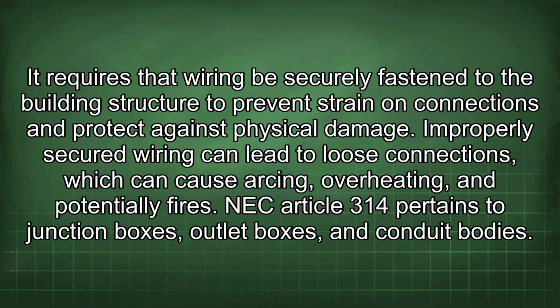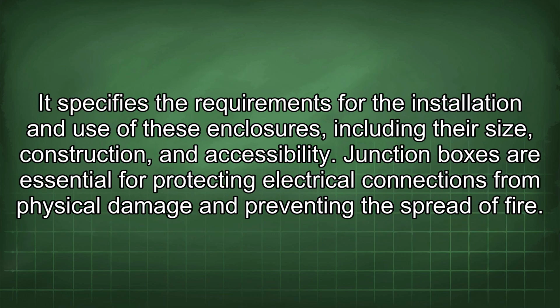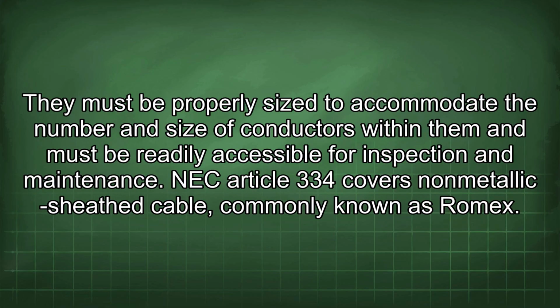NEC Article 314 pertains to junction boxes, outlet boxes, and conduit bodies. It specifies the requirements for the installation and use of these enclosures, including their size, construction, and accessibility. Junction boxes are essential for protecting electrical connections from physical damage and preventing the spread of fire. They must be properly sized to accommodate the number and size of conductors within them and must be readily accessible for inspection and maintenance.